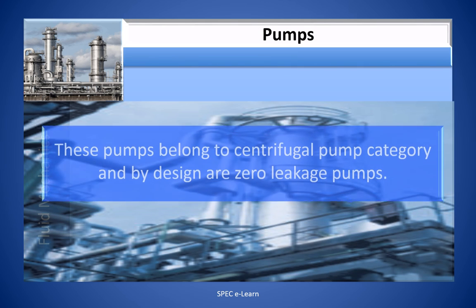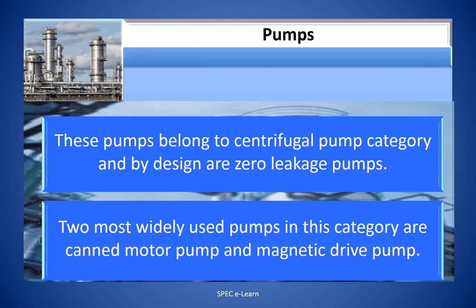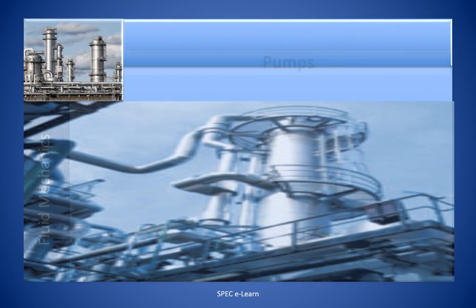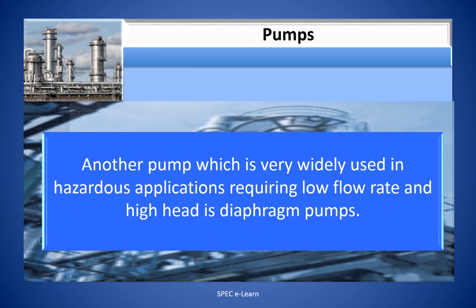These pumps belong to the centrifugal pump category and by design are zero-leakage pumps. The two most widely used pumps in this category are canned motor pumps and magnetic drive pumps. Another pump very widely used in hazardous applications requiring low flow rate and high head is the diaphragm pump.